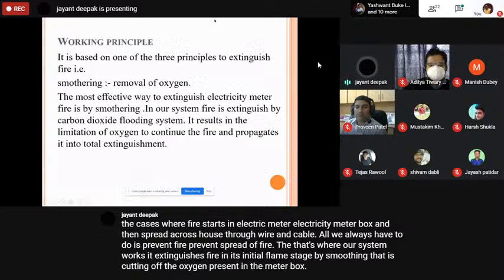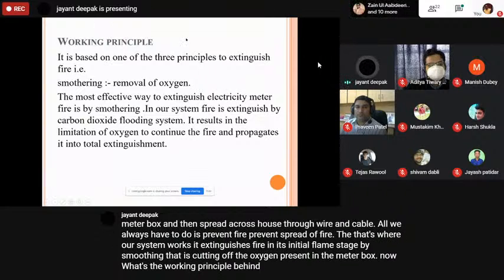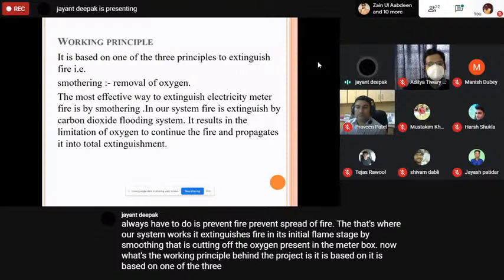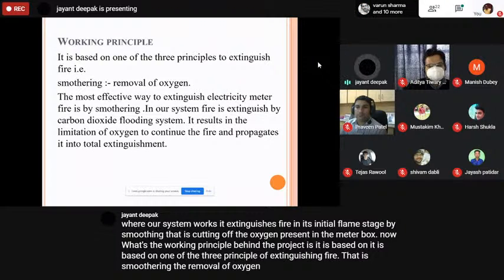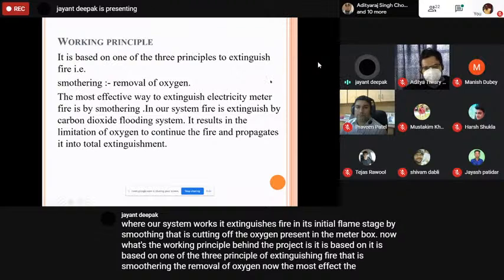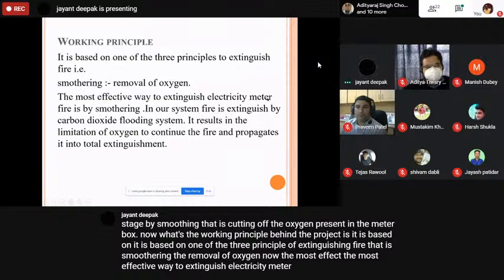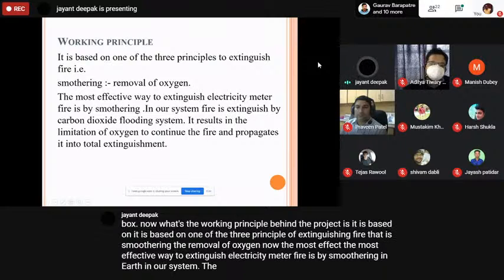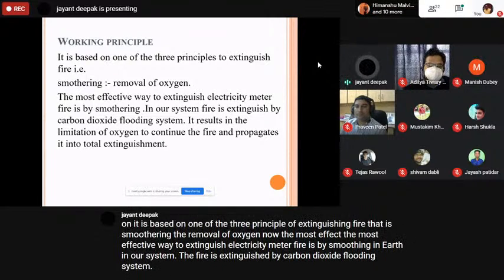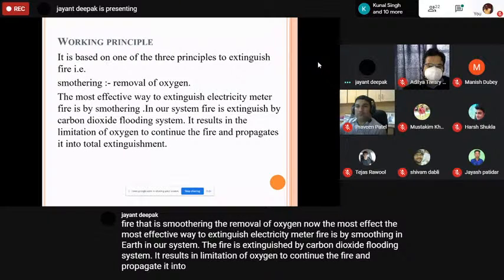Now, the working principle behind the project is based on one of the three principles of extinguishing fire, that is smothering, the removal of oxygen. The most effective way to extinguish an electricity meter fire is by smothering. In our system, the fire is extinguished by a carbon dioxide flooding system. It limits the oxygen available to continue the fire, leading to total extinguishment.